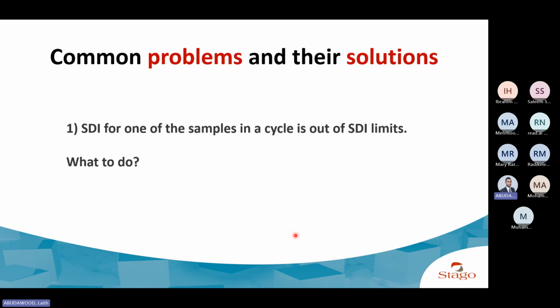Fine. What can we do? The customer will say, okay, at least I need to do some troubleshooting. At least I need to do something. In this case, you can run repeatability and, for example, use a patient sample, run it 10, 20 times. At least you verify the repeatability is okay. And the second thing that you can do is check the reproducibility of the QC. Is your QC over the last 3, 4 weeks, or over the couple of weeks where you ran the EQA sample, okay? Are the CV percentages or SDs within the manufacturer claims of reproducibility? If yes, usually this is an outlier.